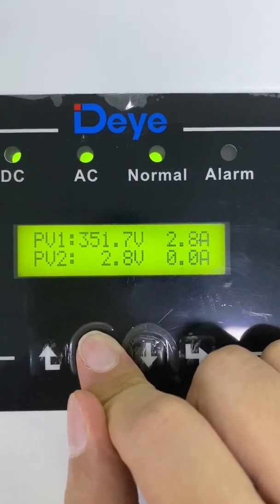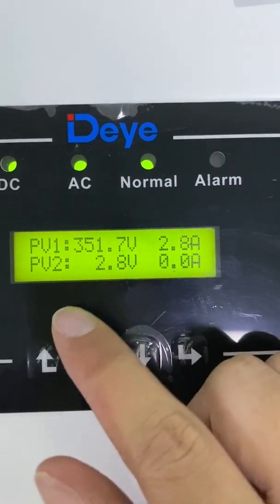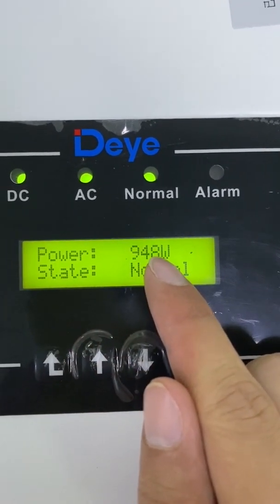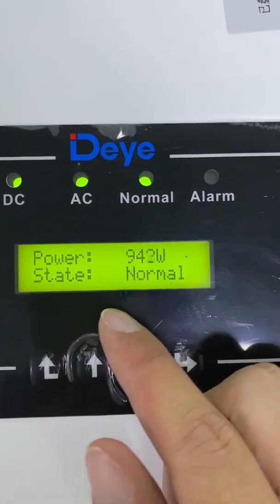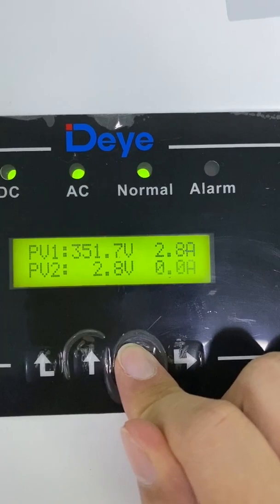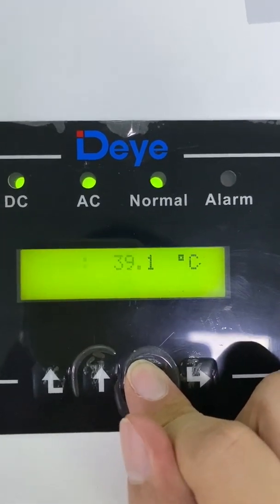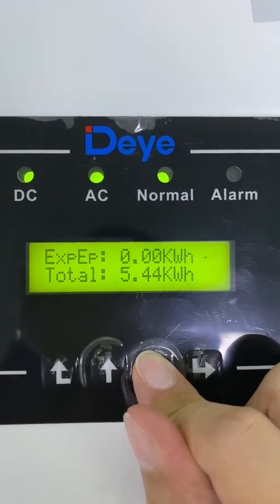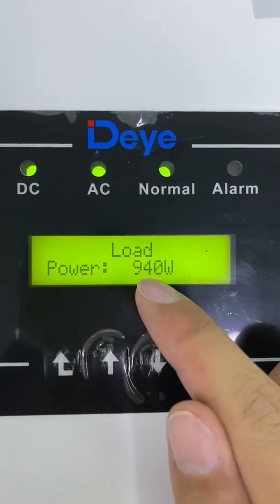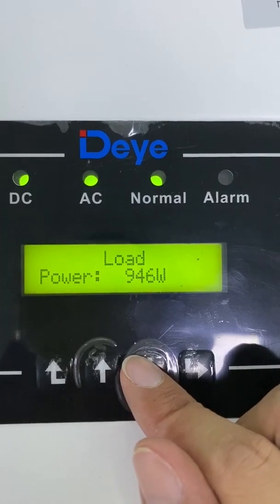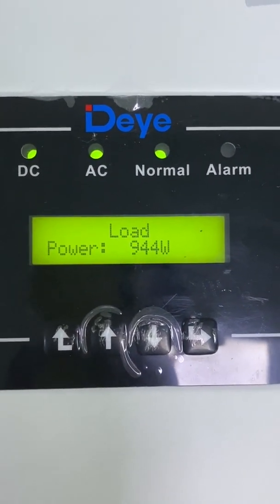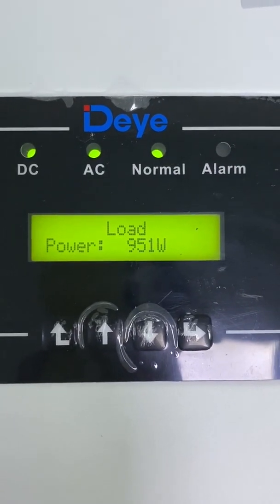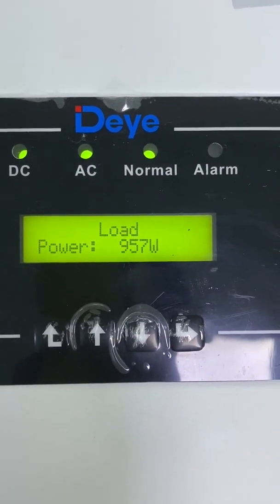Here is the grid voltage, here is the PV input voltage and current, and here is the PV generation — 948 watts. Here is the load power — 944 watts. So in the zero export function, the PV generation power should match the load power, so in this case there is no solar energy flowing to the grid.